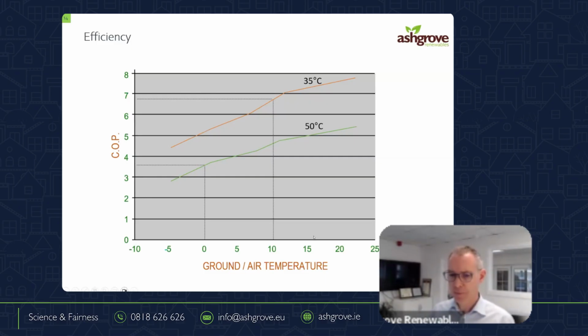Once I put in enough pipe, the temperature in the ground won't drop much below 10 or 8 or 6 degrees. If I don't put enough pipe into the ground, say I put in half a kilometre where I needed 1 kilometre, well, obviously I'm going to start cooling the ground. And then you can see that the ground temperature drops and you can see my efficiency starts to drop away.